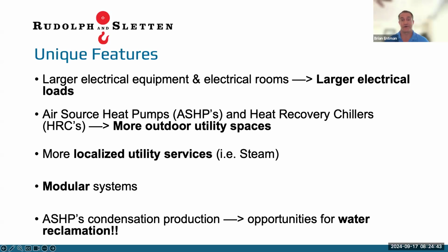The same goes for outdoor versus indoor space for equipment. In California, we're seeing more outdoor equipment—air source heat pumps, air-cooled chillers, and air source/sink heat recovery chillers that can serve dual purpose for both peak design seasons and shoulder seasons, giving you an option when you don't have enough cooling or heating otherwise. But all of this requires larger mechanical yards or roof space, and that has to be part of the design decision conversation.